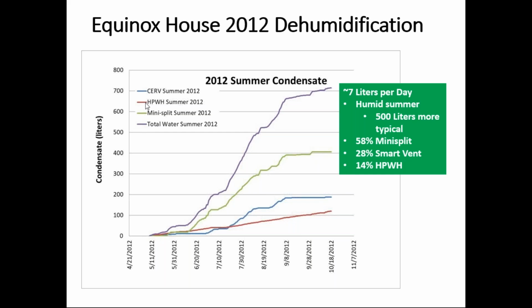Now, if you look at the middle of the summer, over the course of July, going from about 200 liters up to about 500 liters over about a 1 month period, that's about 7 liters per day. And from our example problem for a tight home in Urbana, a 2,000 square foot home with 2 occupants, we came up with about 6 to 7 liters per day. And so we're in very good agreement, and this is without trying to fudge anything. This is real data, condensate data collected every day from each of these systems for 4 to 5 years. And the modeling is taking our average weather and finding out that, hey, these calculations actually work.